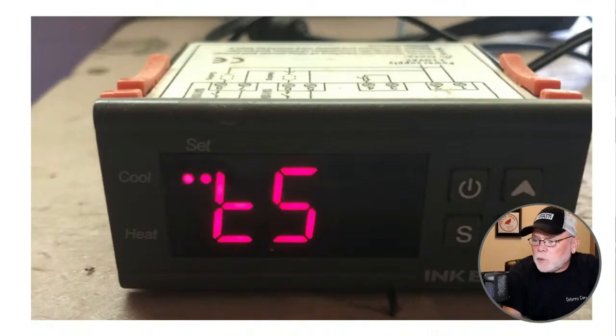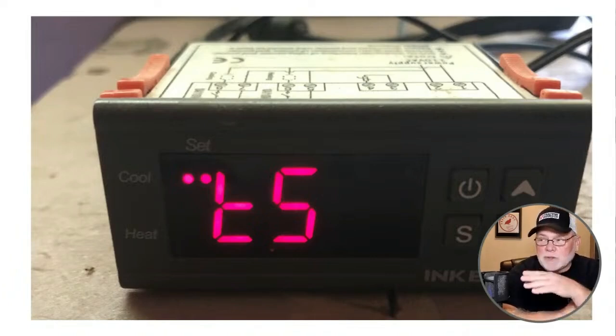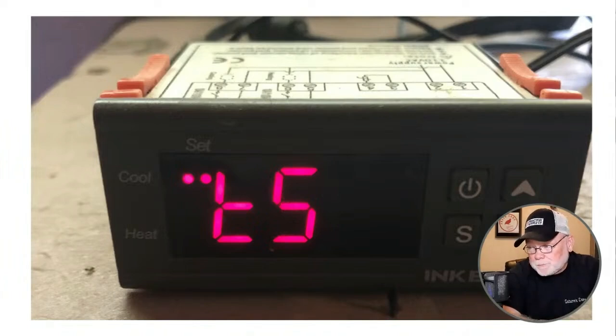Okay, I just wanted to point out, there's 3 settings inside the Inkbird that need to be changed. And this is probably where I run into the biggest issues when people call me up. They have a problem with the incubator, like it's getting too cold, or when it gets to 99, it waits a few minutes before it turns on the heating elements. And that's because there's 3 settings that have to be changed inside the Inkbird. I'm not going to tell you how you get in there to change them, but I will tell you what the 3 settings are, and what values they need to be set to.